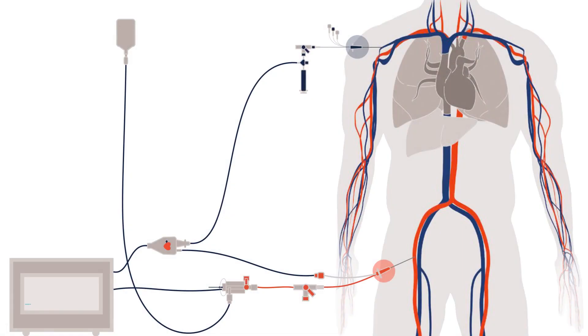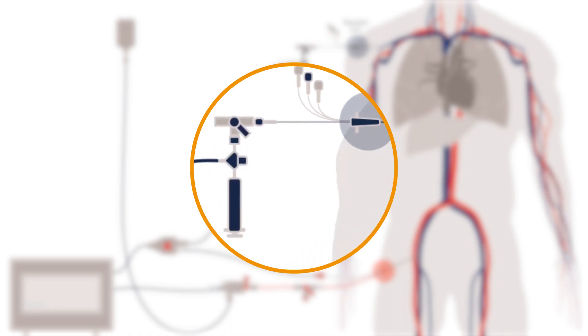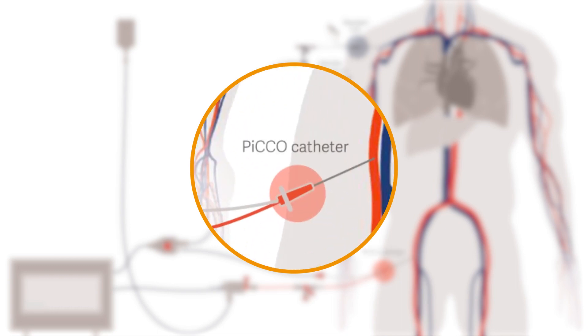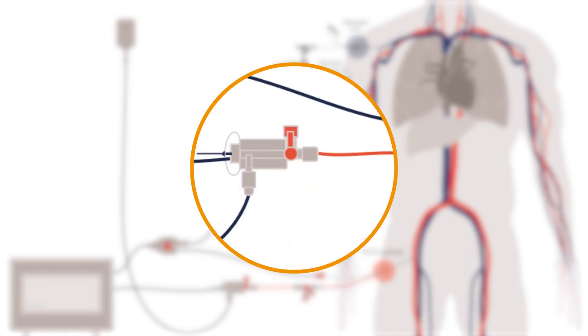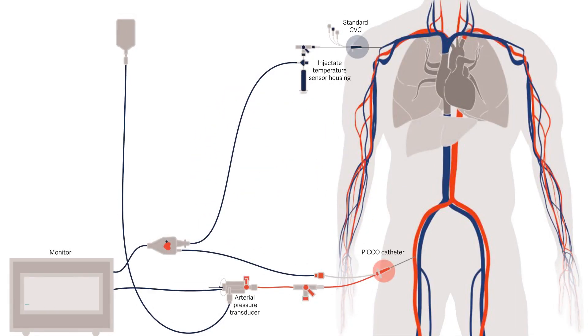To use PiCCO technology, properly set up its equipment. At the patient's side, PiCCO requires a standard central venous catheter, or CVC, with a connected injectate temperature sensor housing, an arterial thermodilution catheter — or the PiCCO catheter — with an integrated temperature sensor at the tip, and a connected PiCCO pressure monitoring kit. All of these are connected to the monitor using cables.